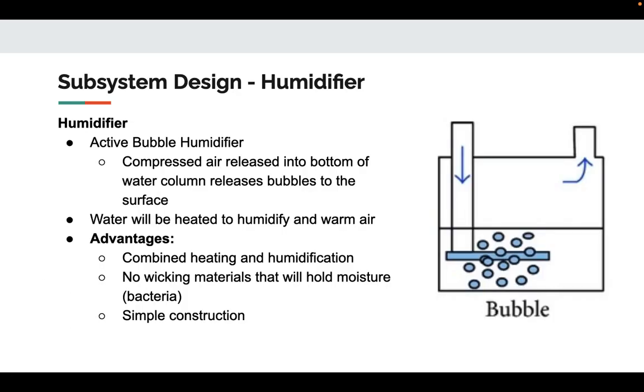So, the subsystem design in terms of the humidifier. The humidifier will be an active bubble humidifier. Compressed air will be released into the bottom of the water column, and this will release bubbles to the surface. So the air is being forced into this water column, and then the bubbles coming up will have water droplets within them. And this is also going to be heated while this is happening. When you heat it, this makes the humidification process easier, and it allows for higher targets of humidity. Additionally, keeping it warmer and preventing condensation will allow for more water droplets to stay in the air and not condense out. And so some other alternatives to this are humidifying via wicking materials or heating.